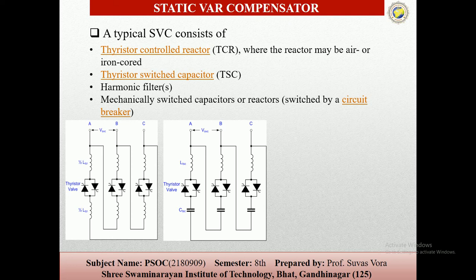So the TCR controls the reactive power by changing the current magnitude passing through the reactor or reactors, and this one is without firing angle control, using step changing reactor options. In the second one, the capacitor's operation is practically the same as the reactor control, but the reactor is replaced by the capacitor. For the capacitor calculation, we have to consider the fully connected or the fully disconnected state of the capacitors.